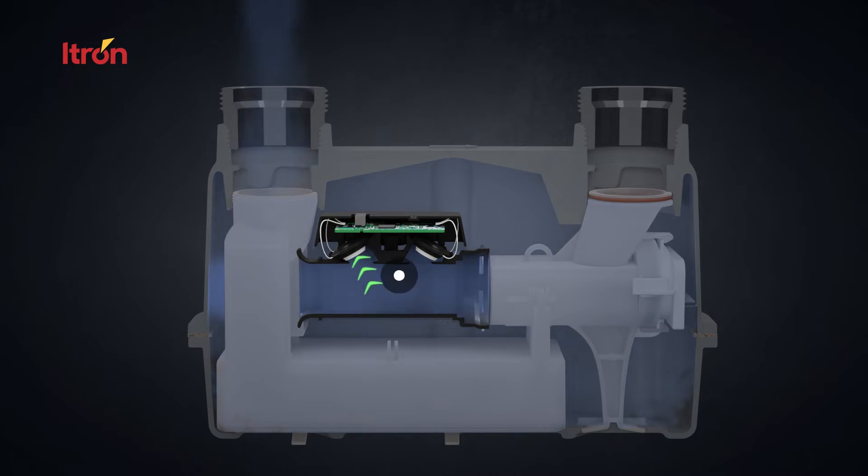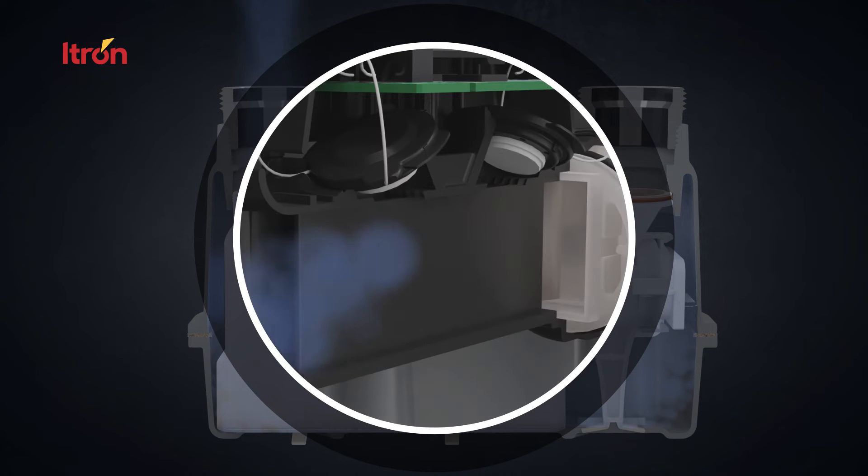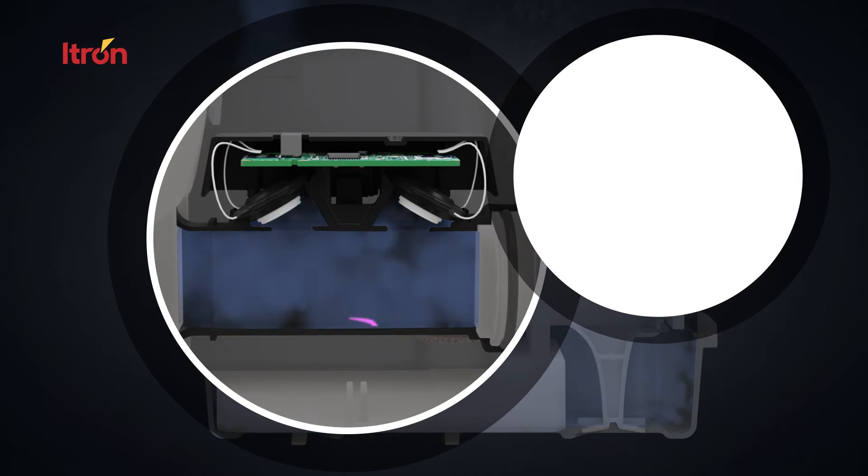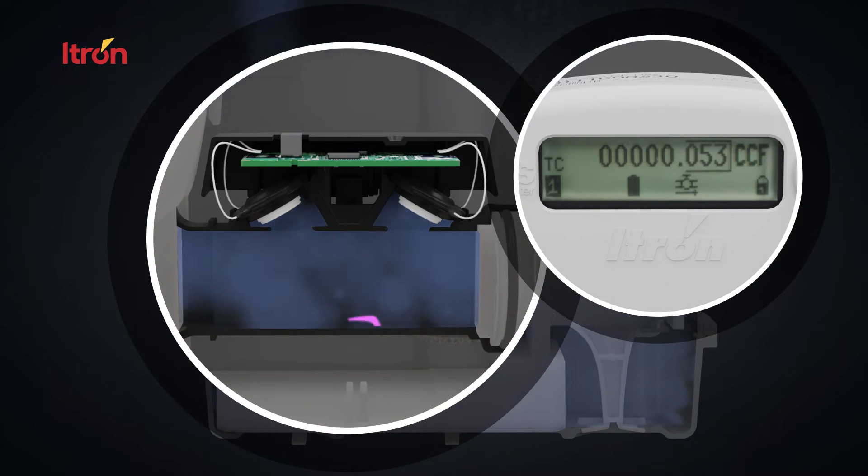INTELIS uses time-of-flight measurement principle utilizing two ultrasonic transducers. A signal is sent from the upstream transducer to the downstream transducer and then in reverse. The time to go from upstream to downstream indicated by the purple arrows is faster than the reverse shown in green. The time difference between both directions is used to determine volume.